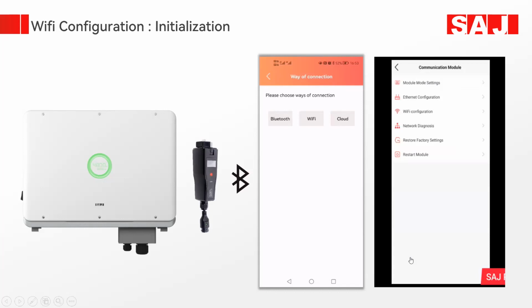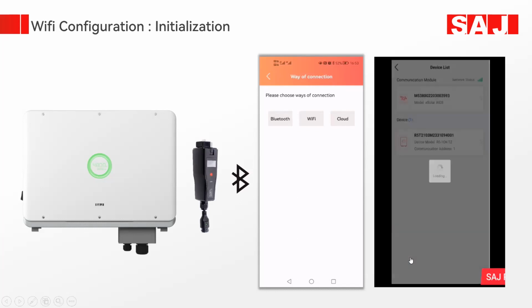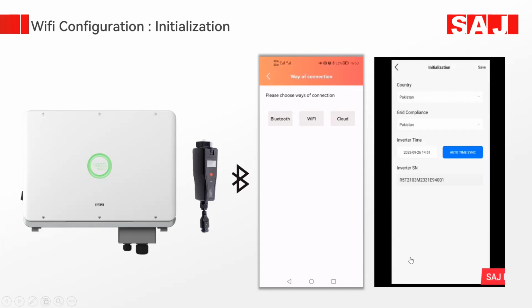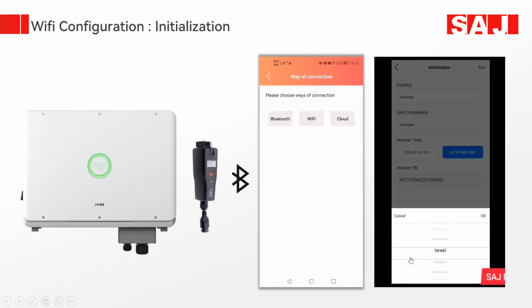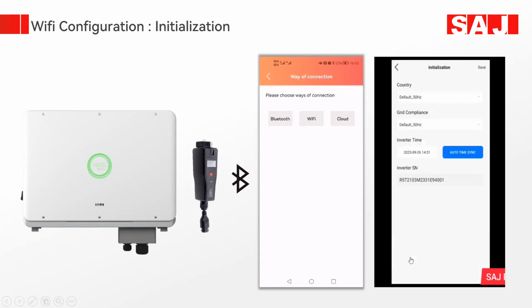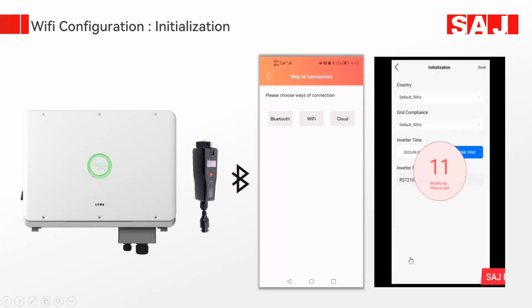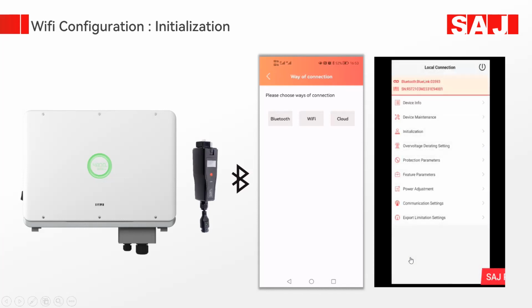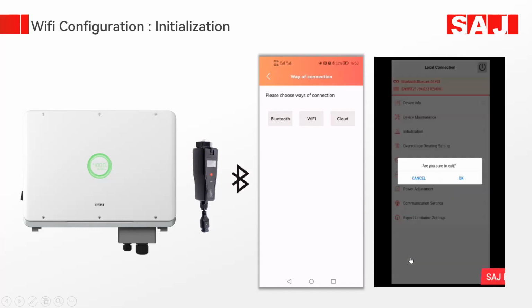if you have an ethernet connection, then you can change the ethernet configuration. You can also configure through an ethernet connection, and you have to go to the initialization setting for the country grid compliance setting. If you don't configure the grid compliance setting, then our inverter will not start production. If you have stable grid voltages, then you configure the country Pakistan and grid compliance Pakistan. And if you have some voltage issues at site, fluctuation in the line to line voltages, then you can configure the default 50 hertz. So after that, you can exit the process.